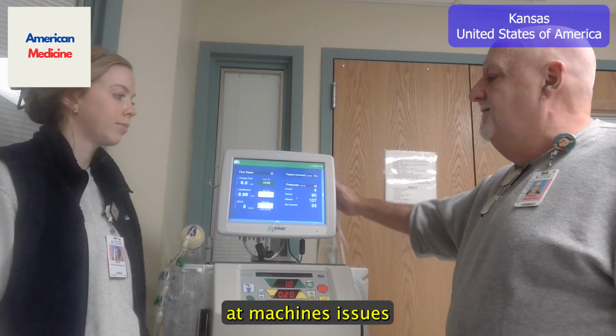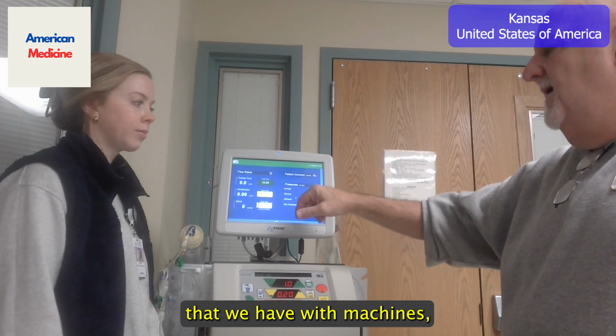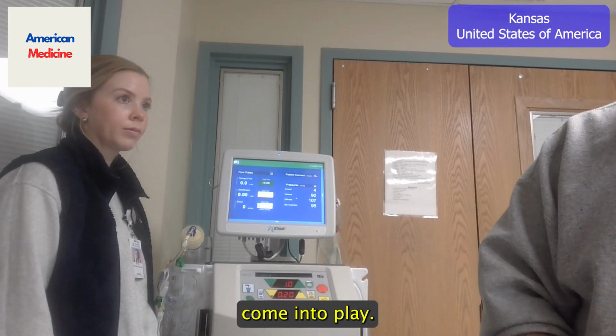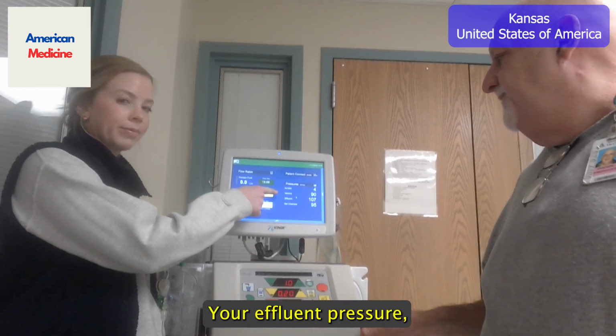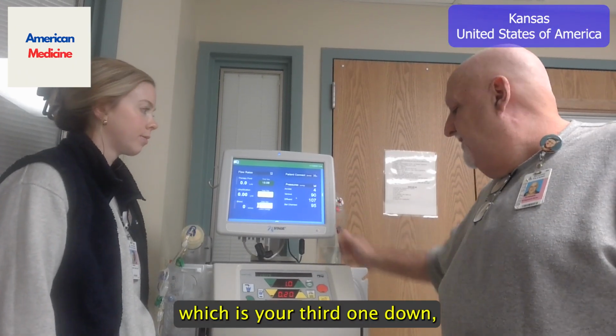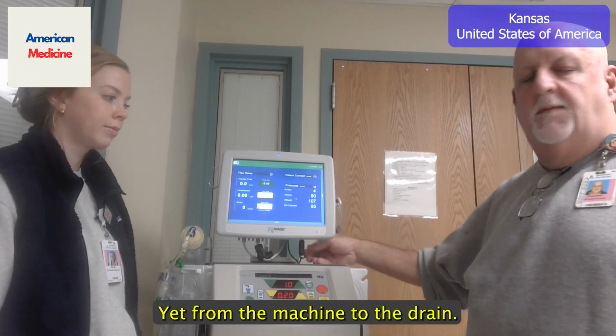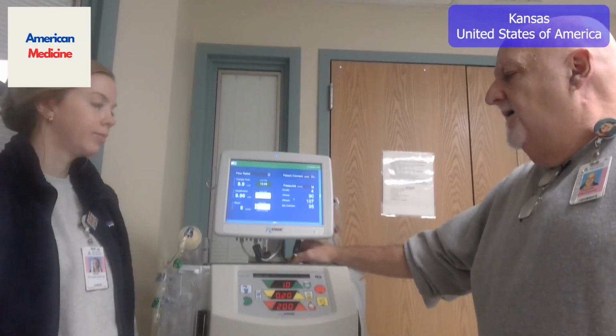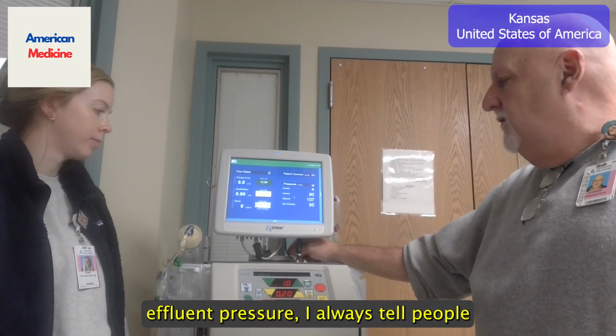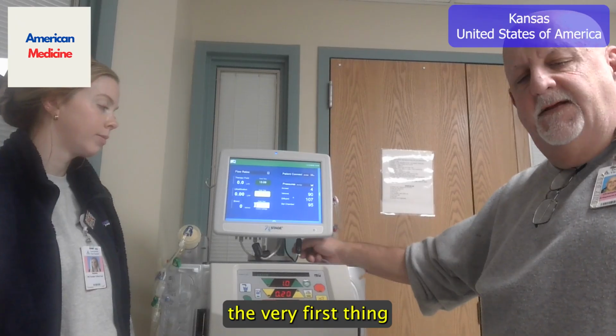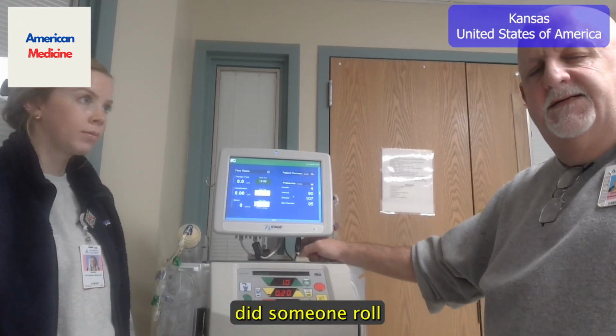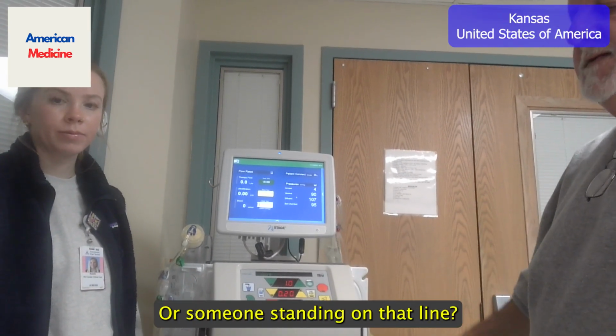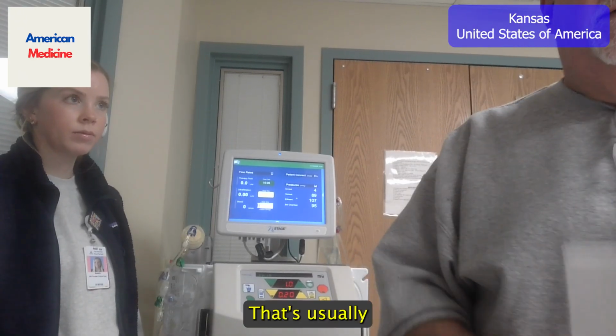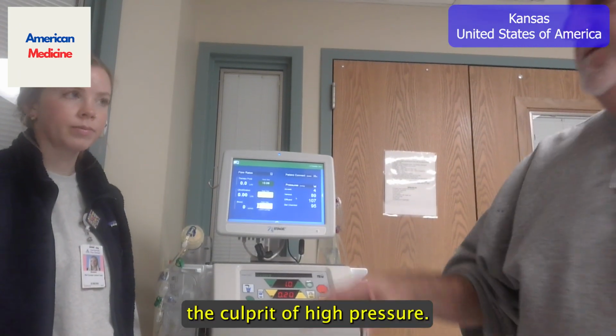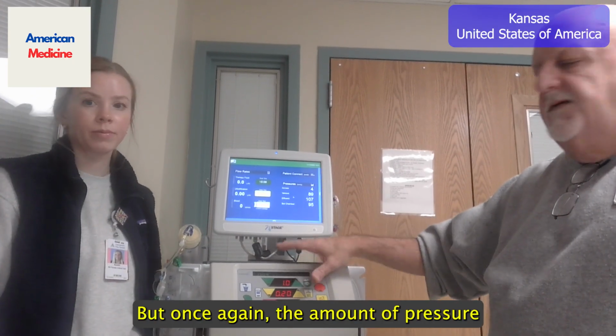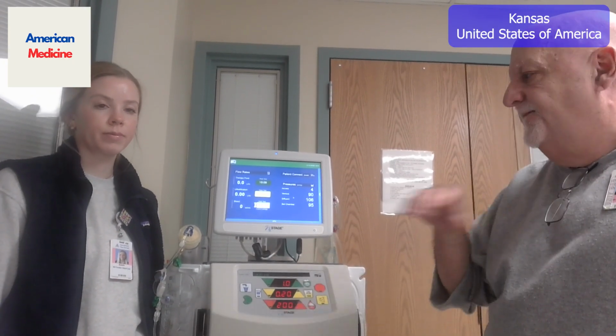Now, when we start looking at issues that we have with machines, that's where your last two numbers come into play. Your effluent pressure, which is your third one down, is the amount of pressure it takes to get from the machine to the drain. So anytime we get a high effluent pressure, I always tell people the very first thing you should think of is, hey, did someone roll something on that line, or is someone standing on that line? That's usually the culprit of high effluent pressures. But once again, it's the amount of pressure it takes to get from the machine to the drain.